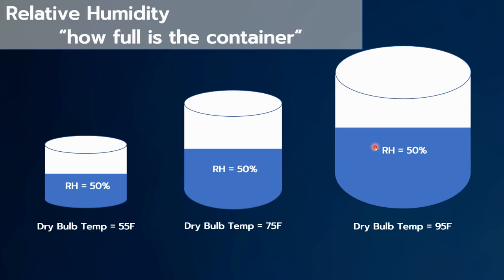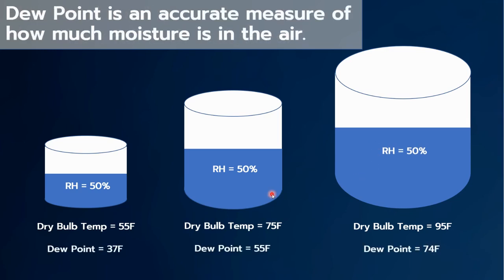When we look at dew point, let's say we took the first condition — RH of 50%, dry bulb of 55 — and calculated the dew point, which in this case is 37. We did the same for the other two containers: the dew point would be 55, and this dew point would be 74. Now as you can see, as the volume of water increases, our dew point increases.